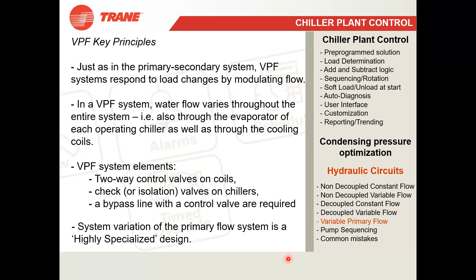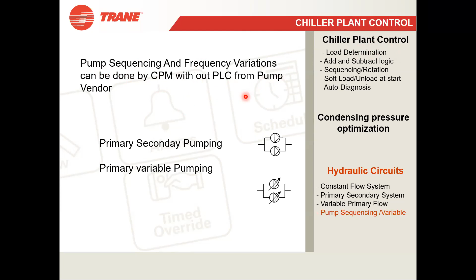Now, in my first slide I told you, if you are not using the CPC, what options do you have? You can put PLCs on the pump side, because all the pump manufacturers now provide PLCs. You can take that and integrate it with the BMS. But then you can only monitor. You cannot control or regulate anything. But if you use this CPC, then these PLCs are not required. This CPC can do everything. You have now understood, I hope, that pump sequencing and frequency variation on the pump side can also be done using this CPC. So these PLCs on the pump side will not be required, and you can save there also.